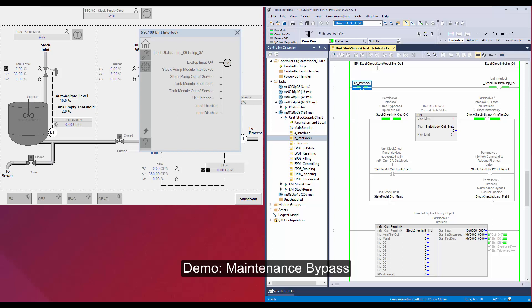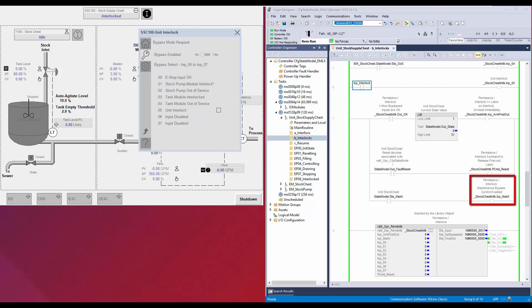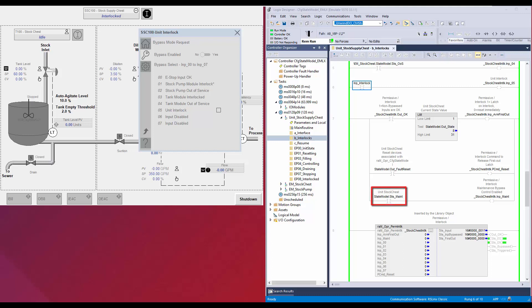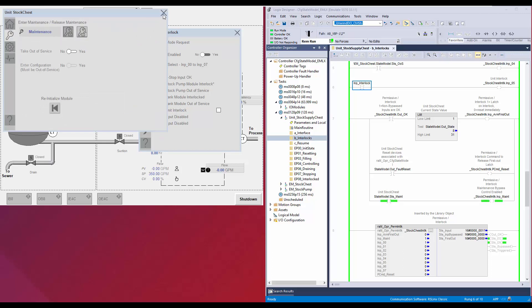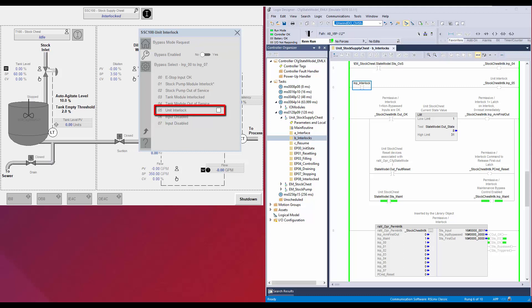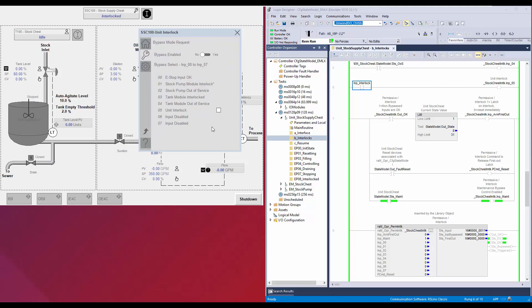We will now see the maintenance bypass option. I will fail the input. To bypass, I have opened the settings tab. The bypass enabled toggle switch is disabled as the maintenance input to the instruction is off. Since I have linked this input with the maintenance of the unit module, I will switch to maintenance control in the unit state model first. Now I am in maintenance mode, so input maintenance is on. The bypass enabled toggle switch is also enabled. You can also notice that only the unit interlock input is allowed to be bypassed. This option is to be selected from the configuration tab, which tells which inputs are allowed to be bypassed.